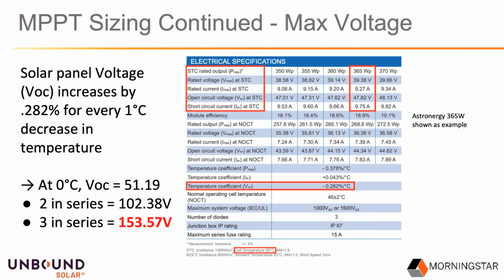So if I look at an example using 0 degrees Celsius, which is freezing, that's a 25 degree change in temperature from the cell temperature in the specs. So 25 degrees times 0.282%, it's just over 7% change in voltage. That's simply how you could calculate that voltage change depending on a given change in temperature. So our voltage is going to be just over 7% higher at 0 degrees Celsius. In this case, that actually pushes the panel a little bit over 51 volts, 51.19 volts for each panel. So 2 in series, you're at 102 volts. 3 in series, you could actually exceed 150 volts. So this just shows us that at 0 degrees Celsius, this panel is going to open circuit at 51.19 volts after we correct for temperature.